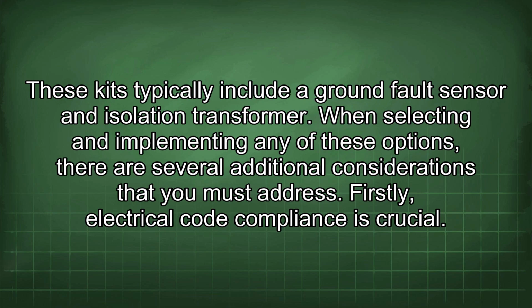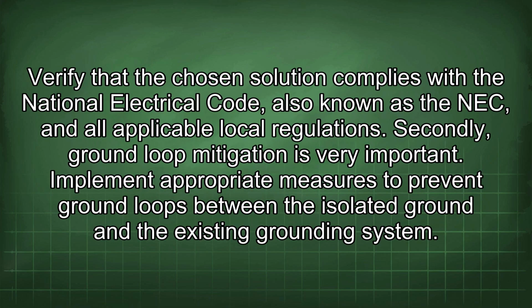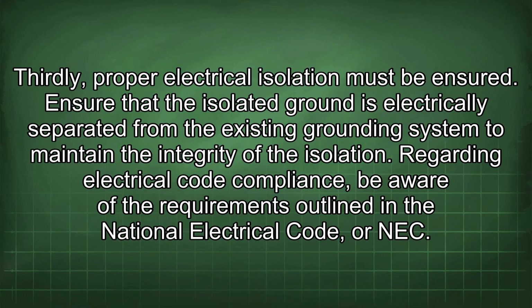When selecting and implementing any of these options, there are several additional considerations that you must address. Firstly, electrical code compliance is crucial. Verify that the chosen solution complies with the National Electrical Code, also known as the NEC, and all applicable local regulations. Secondly, ground loop mitigation is very important. Implement appropriate measures to prevent ground loops between the isolated ground and the existing grounding system. Thirdly, proper electrical isolation must be ensured. Ensure that the isolated ground is electrically separated from the existing grounding system to maintain the integrity of the isolation.